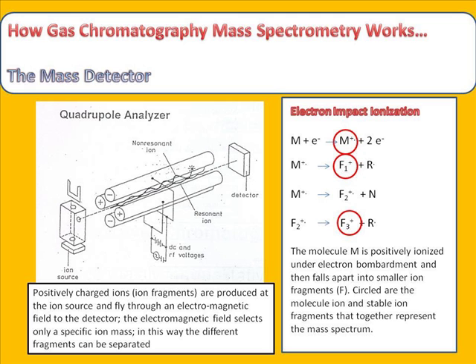The molecule ion and the stable ion fragments are detected by the quadrupole mass analyzer. This happens in the way that particular ions with a specific mass fly through these four rods, as you can see in the left figure. There is an electromagnetic field established between these quadrupole rods, and this electromagnetic field will only let one particular ion fragment with a very specific mass through at a time. In this way, particular ion fragments, or the entire group of ion fragments, can be monitored.